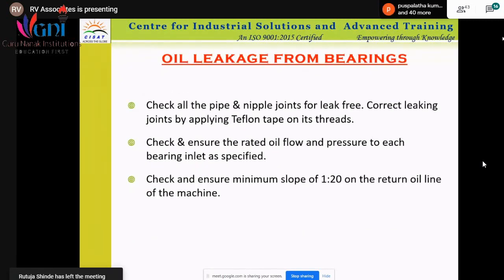Then oil leakage from the bearing. Oil leakage happens because of failure of the gaskets. If the gaskets fail, there will be an oil leakage. My standard practice says that there should not be an oil leakage from a motor as well as a transformer. In no case should there be an oil leakage. So you have to continuously check and monitor the system. You have to monitor the pressure of the pump. Whatever the hydraulic pump is pumping, the oil pressure has to be monitored.